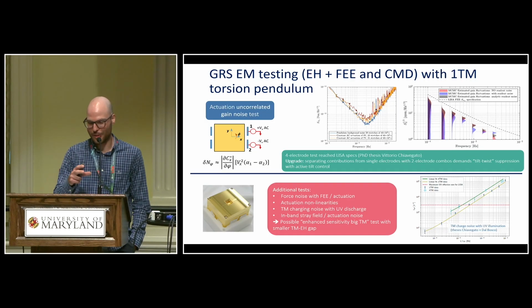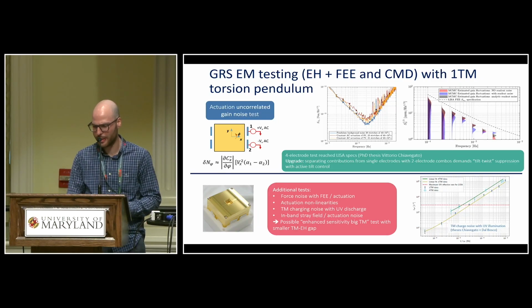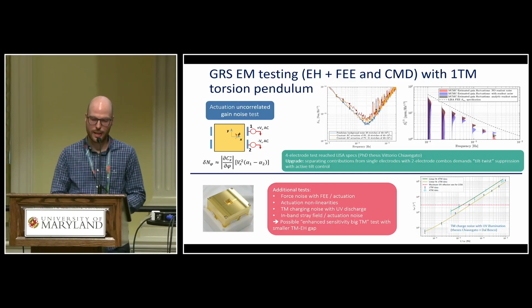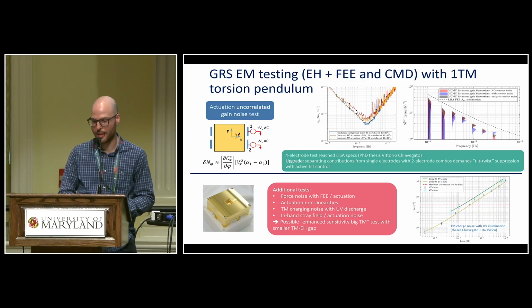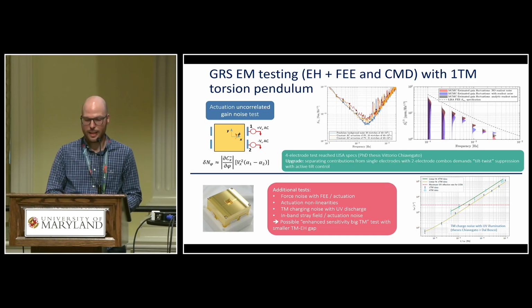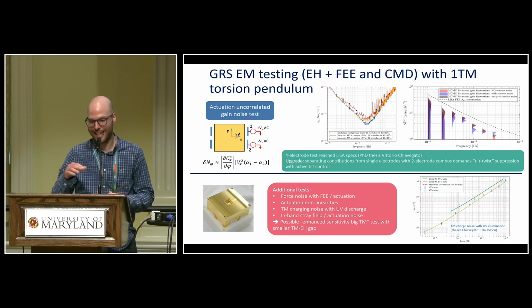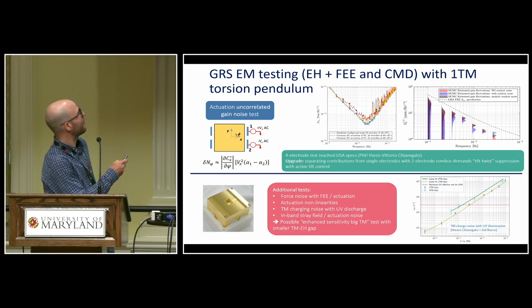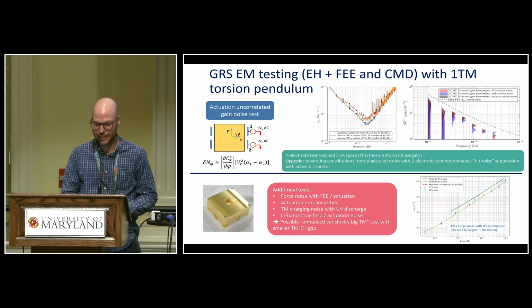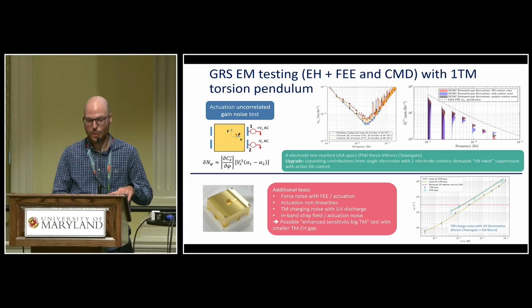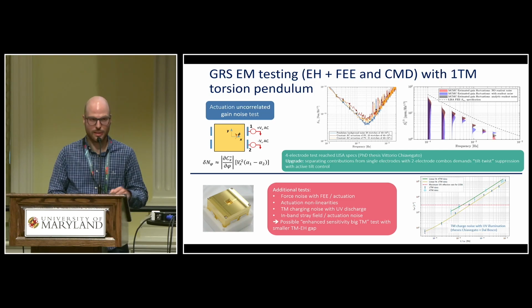Here I also explain some of the measurements that we can do in more detail. For example, a very important measurement, conducted by Vittorio Chiavegato, a former PhD student of our group, is to measure the noise related to uncorrelated gains in the actuator, in the front-end electronics. Imagine that we have some potential applied to two of the electrodes, and the nominal amplitude of this potential is the same. But there is a fluctuation in this potential due to random and uncorrelated variation of the gain of the front-end electronics on the two electrodes.